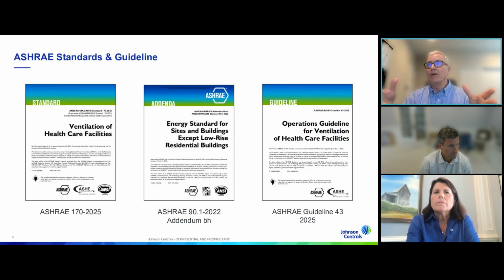One of the big things with healthcare, and I'm sure you're all aware of that, is that hospitals are typically 3 times more energy intensive than a commercial space or other types of buildings. So already we have very high energy use intensity rates. But on top of that, if we look at some of these critical spaces like an OR, they're typically another 3 to 6 times higher in energy use intensity within the hospital itself. So we really want to focus on the energy consumption within those spaces, because that's typically our lower hanging fruit when we're looking to scale back our energy costs.